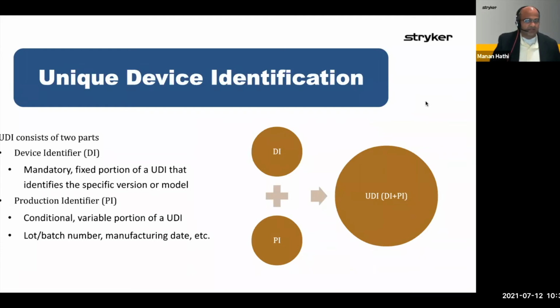So just how does UDI provide unique device identification? Really, it does this by breaking the UDI code into two parts. One is a fixed mandatory portion of the UDI, which is called the device identifier. And that really is identifying the specific version or model of the device. So it's usually issued by a special accredited issuing entity. GS1 is an example. There's also HIBCC and ICCBBA, but generally it is an accredited issuing entity that provides a global numbering scheme, such that they are responsible to make sure that when you are assigned a number, no other medical device is given that same number.